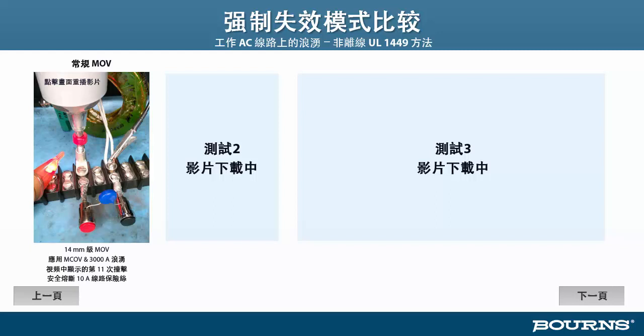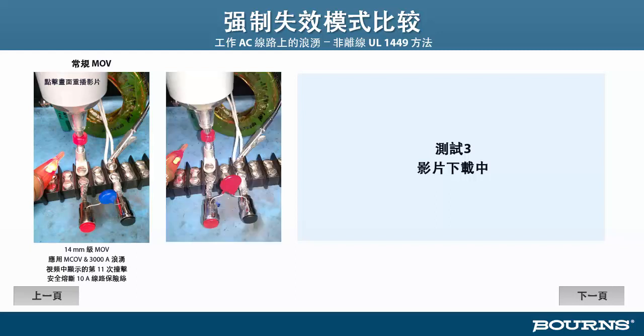The second part in the middle is a thermally protected MOV. Again, we're applying the rated voltage to it, and we're applying its rated 3000 amp surge. This time, the failure occurs at the 8th surge. Ready? Here we go. This one failed in a more dramatic fashion. You can see that some of the epoxy coating was broken off and ejected from the part.